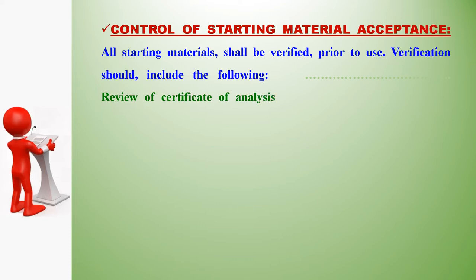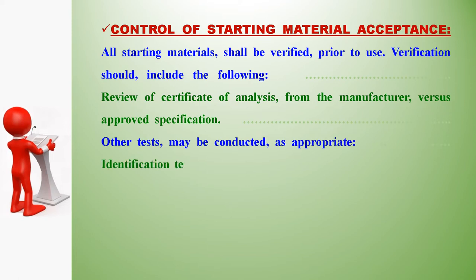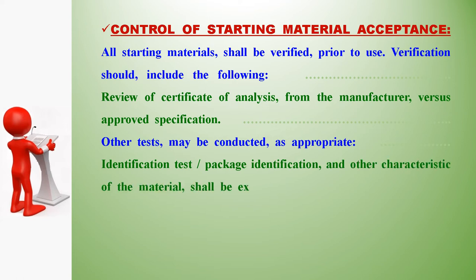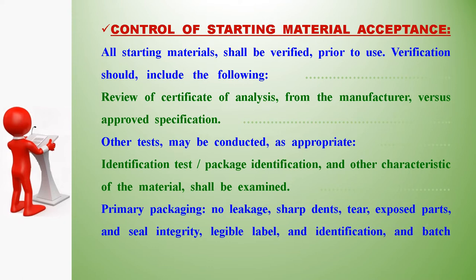Control of starting material acceptance: all starting materials shall be verified prior to use. Verification should include review of the certificate of analysis from the manufacturer versus approved specification, and other appropriate tests. Identification tests, package identification, and other characteristics of the material shall be examined, including primary packaging for leakage, tears, and seal integrity, legible label, identification, and batch number. Frequency: every batch of manufacturer's batch.